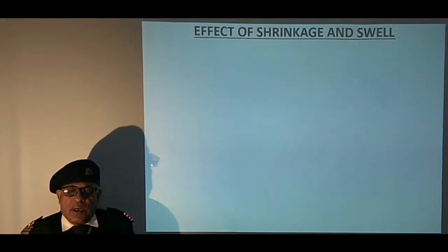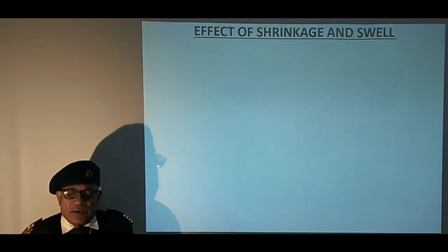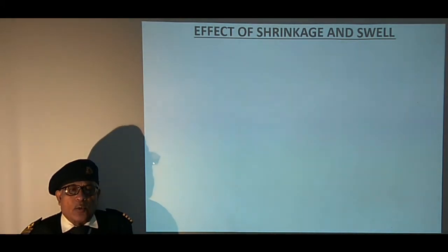In large capacity water tube boilers, there is additional difficulty in maintaining the water level due to the phenomena of shrinkage and swell when the boiler load changes suddenly. Precise control of water level is thus necessary, as a water tube boiler holds a small quantity of water and a large quantity of steam. The reason for swell and shrinkage will be discussed now.